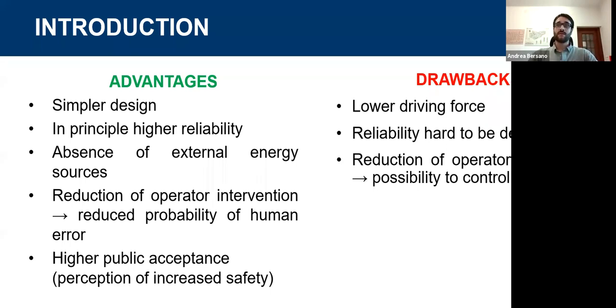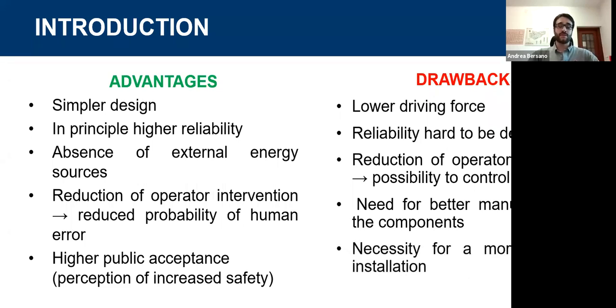And so, on the other side, it is not so easy to control and eventually to regulate the performance of these systems. There is the need for better manufacturing of the components, because this is related to the first point of the drawbacks, so the lower driving force. Since we have a lower driving force, we need, for example, to have a very low roughness of the piping, very low local loss coefficients in order to achieve natural circulation. So we need also some better manufacturing of the components. A more controlled installation, because it's more important to ensure, for example, a perfect verticality or horizontality of the components.